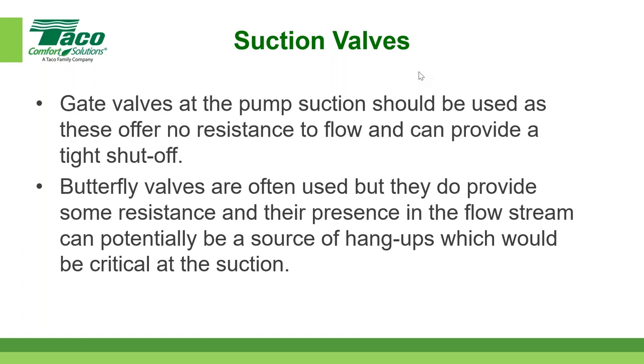Suction valves, right? This is some basic information. Put in your details, maybe gate valves on the pump suction. Why? Because they don't offer resistance to flow and can provide a tight shutoff, right? So it's a simple gate valve. Many times we see butterfly valves, but they do provide some resistance, right? So you're affecting that flow a little bit, and can potentially be a source of hangups, which would be critical at the suction. So something to consider. That's a simple detail change, and maybe it's already on your details.